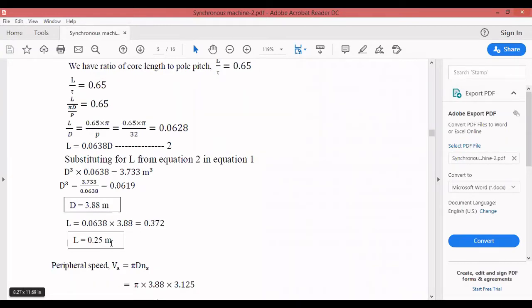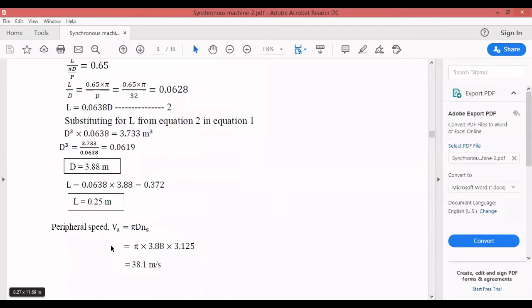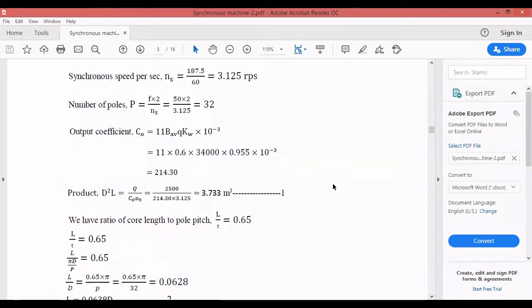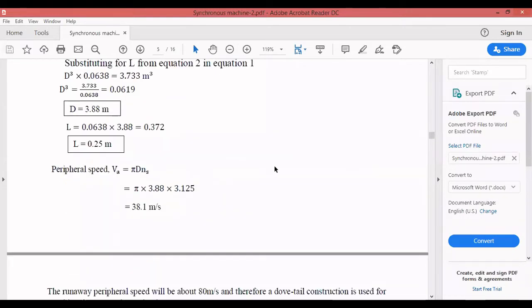Comparing D and L: for an industrial motor D and L are around 0.2 to 0.3 m and rarely exceed 1 m, but for an alternator D is typically much larger — here D = 3.88 m and L = 0.25 m. Since they specified circular poles, we now calculate the peripheral speed: va = π × D × ns = π × 3.88 × 3.125 ≈ 38.1 m/s.